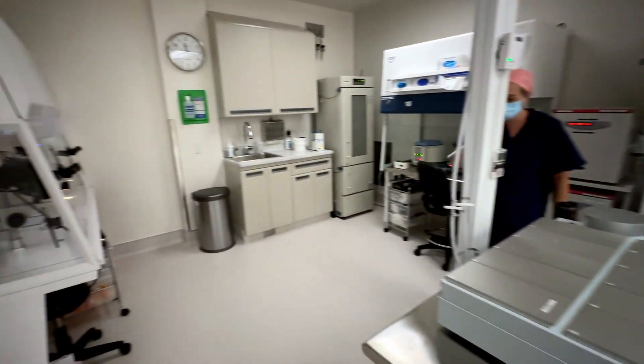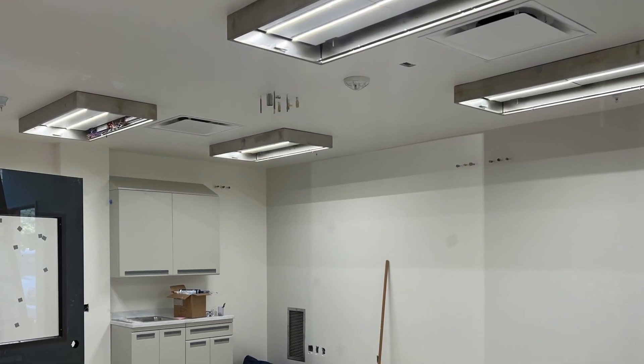During this process, we expanded our laboratory square footage by 50%. Adding a hard-lid ceiling to the space allowed us to create a pressurized room to ensure that there was no outside air flowing into the area. We built our new air filtration system with the best professionals specializing in IVF laboratory air quality.